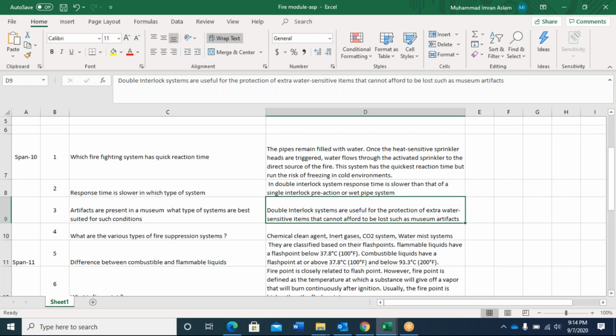But in the double interlock system, we have two things available: the detection device and the automatic sprinkler. This is controlled by a control panel, which has circuits configured with what we call cross-zoned operations. One circuit is connected to the electrical detection system, and the second is to the low air supervisory switch, as we call it. In this double interlock system, when the supervisory switch is activated, the air will be released. Then the electrical detection system also needs to detect. So both systems should work.